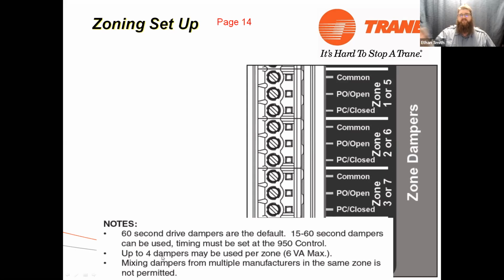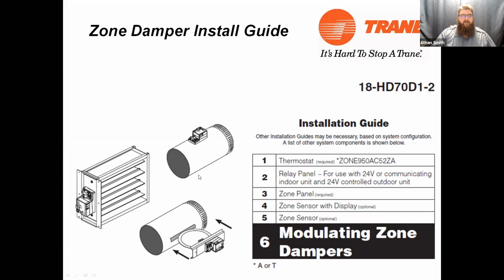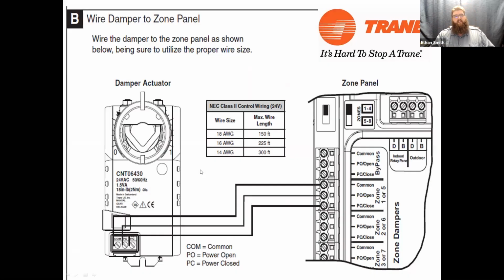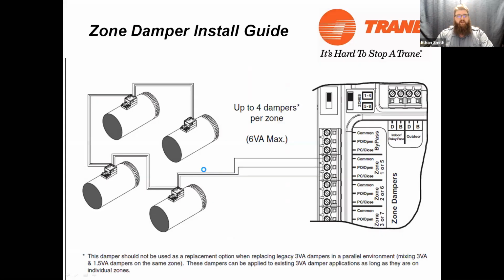Up to 4 dampers can be used. Those are the Trane dampers, obviously. If you use somebody else's, the VA rating maximum for each damper control is 6 VA. So we can use up to four dampers per zone. And I thought I had a diagram here. I do. So we'll get back to that.